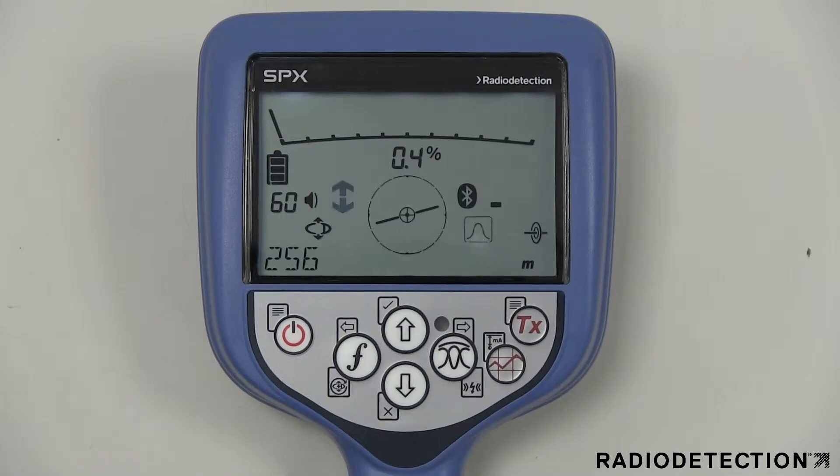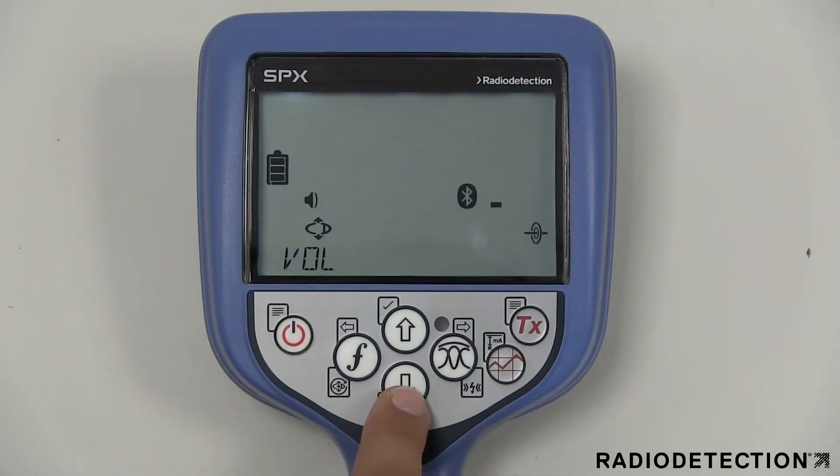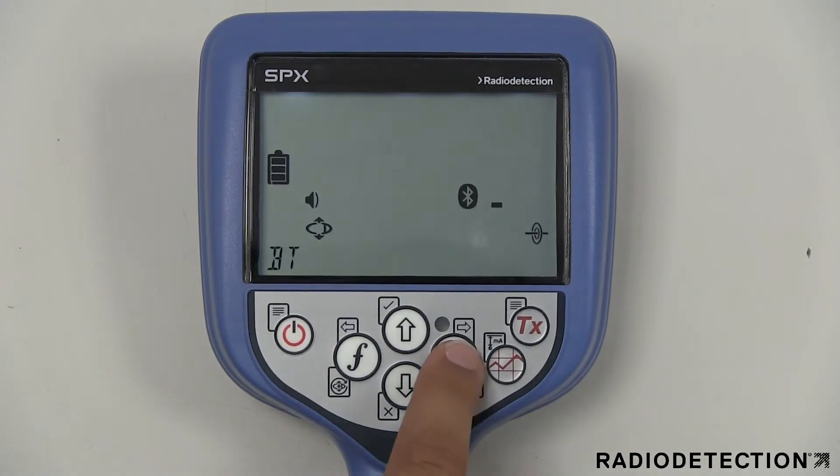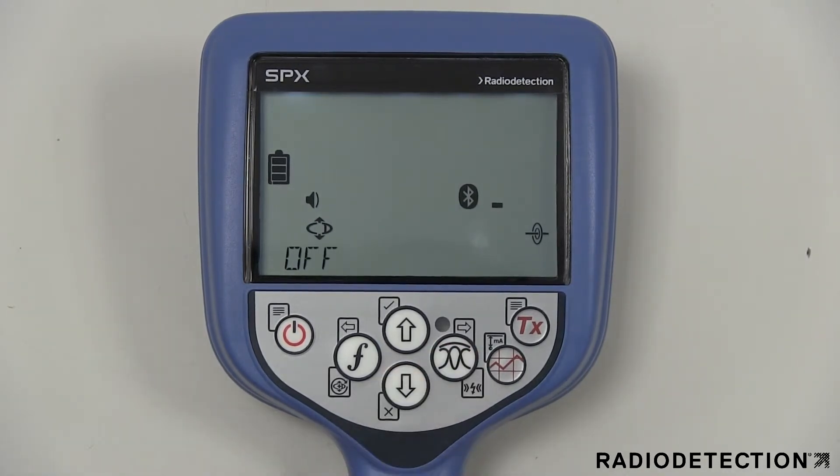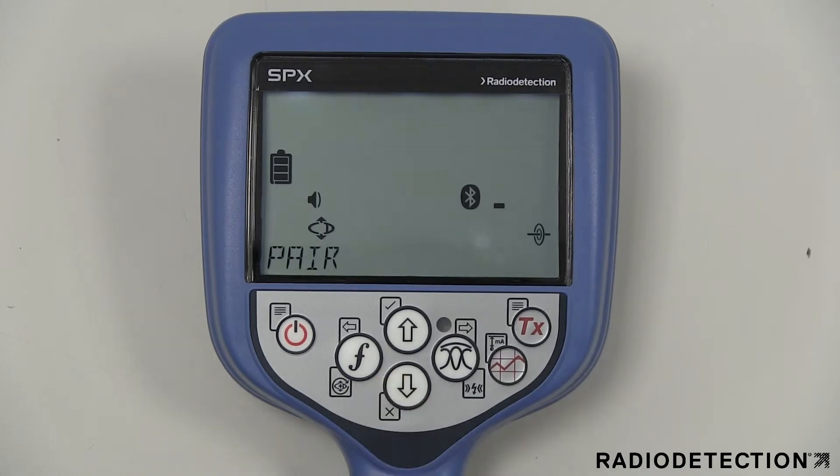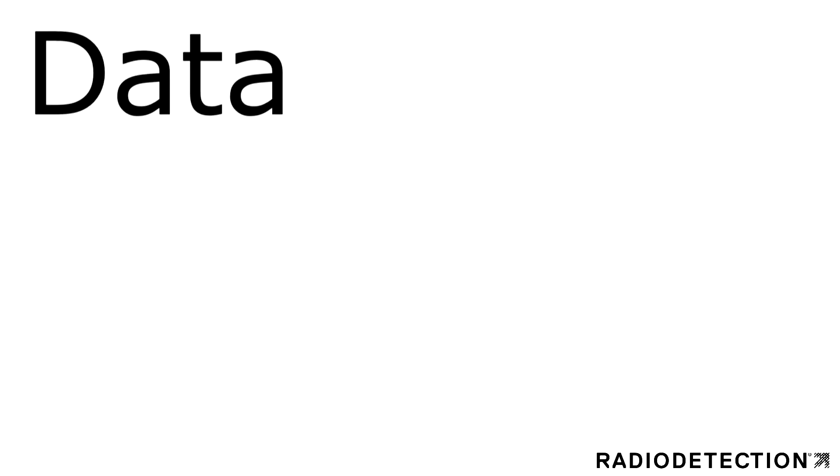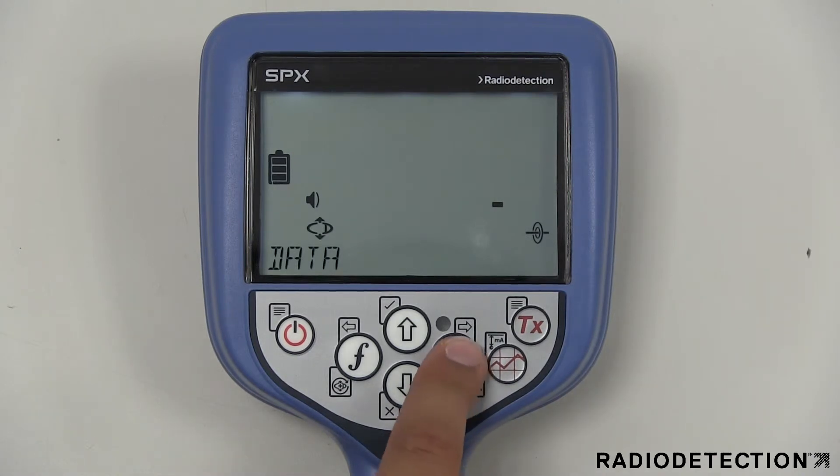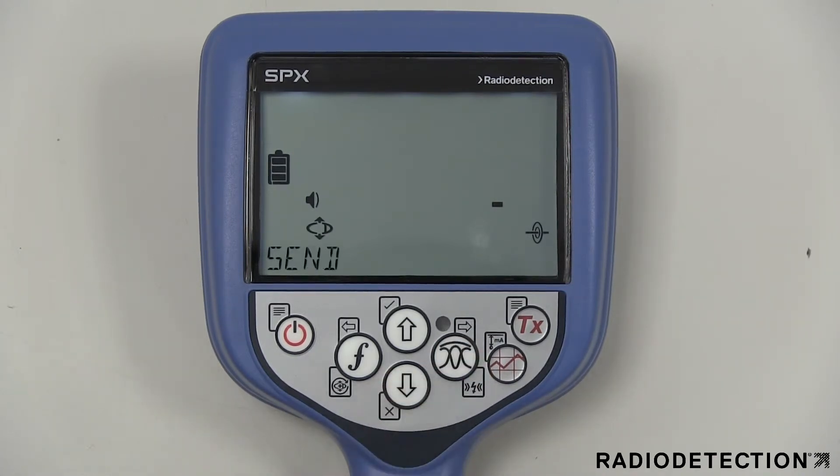The BT menu option allows you to manage the Bluetooth connection between the locator and the TX transmitter and other devices such as PDAs. The protocol option allows you to tell the locator what format the data should be sent in to the external device. The reset option can be used to forget all connections on the device. The pair submenu has two options allowing you to connect to a TX transmitter or an external device. The data menu option allows you to delete or send saved survey measurement data to a connected device via Bluetooth connection. The exit option can be used to disable the communication channel.